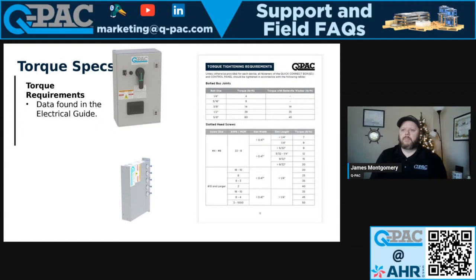Sean's a good question. The main reason people ask this, and I know he knows why he asked it, is that when we're talking actual comms, whether we're passing data, RS-485, or 232 or any of the other data forms, you want to have some kind of shield because of different types of induced voltages that can happen. You can pick up different types of flux from different components, and they can contribute to distortion in your signal. Having that extra drain there will accept those and give it someplace to go, as opposed to getting into your comms conductors. In the comm world, they call that crosstalk. In the electrical world, you're just calling it interference, whether that be radial or lines of flux. I hope that answered your question, Sean.